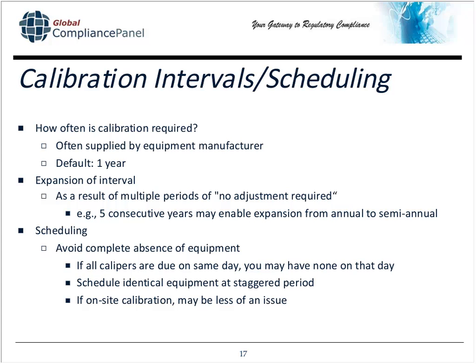When you schedule your calibration performances, make sure that your scheduling avoids complete absence of equipment. Now, it's going to be kind of difficult if you have one piece of tester calibration equipment. Maybe you have only one high pot tester, for example. They cost a couple of bucks. In those situations, you want to make sure that you have on-site calibration, because it makes it less of an issue. Actually, it makes it no issue, because the only downtime is when calibration is actually being performed.